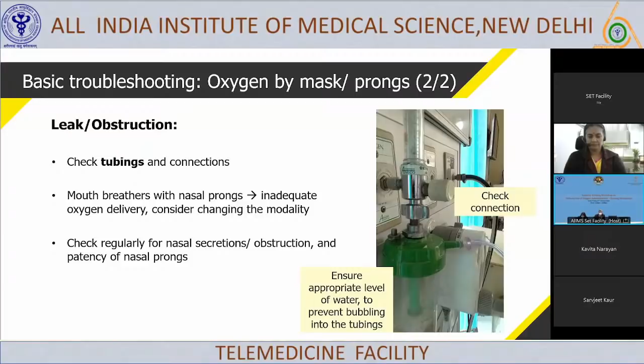If you have a humidifier, then make sure that the water level is appropriate and there is bubbling happening, and this would be demonstrated in the video. Make sure that if you're using a humidifier, the washers are in place so that there's no leakage happening, and the connections are all tight and there's no leakage happening there.